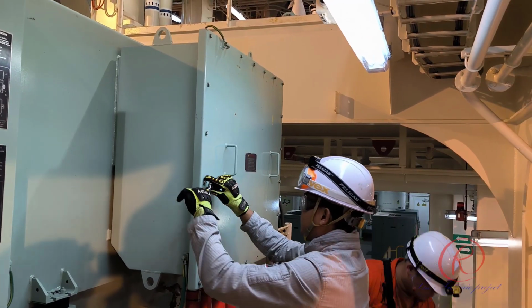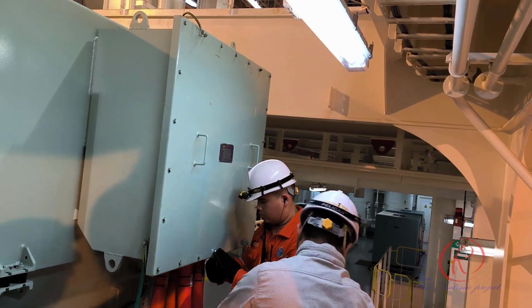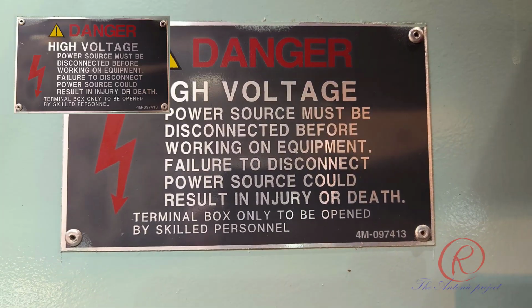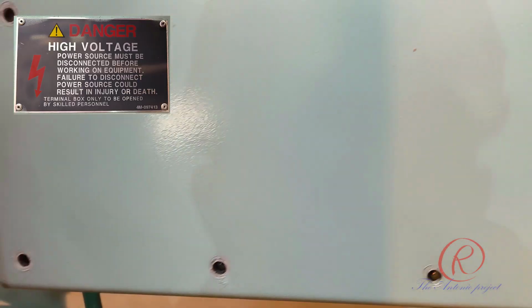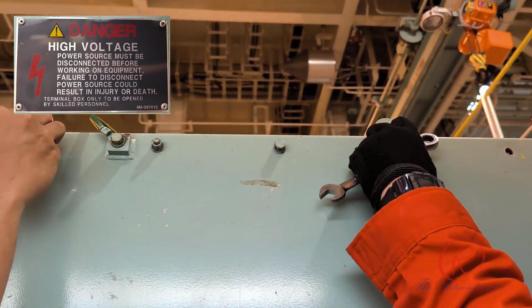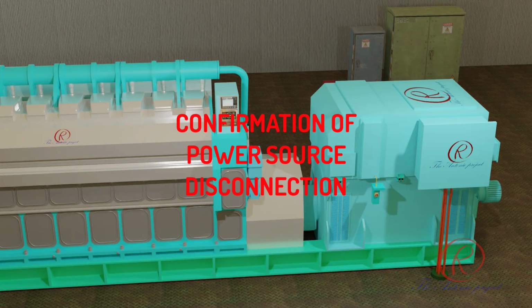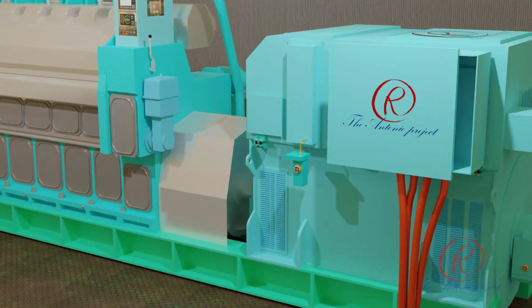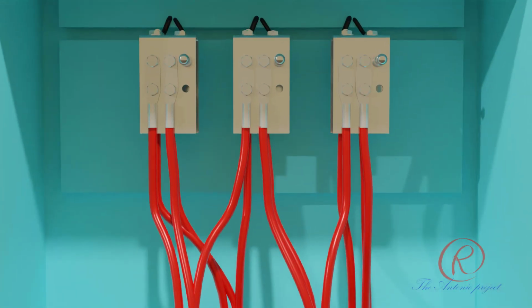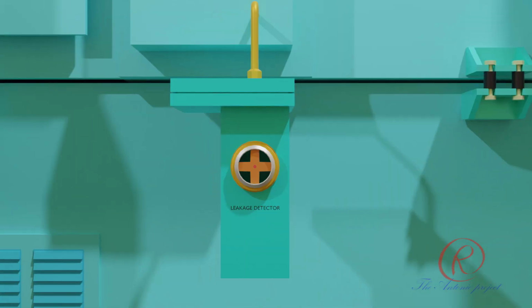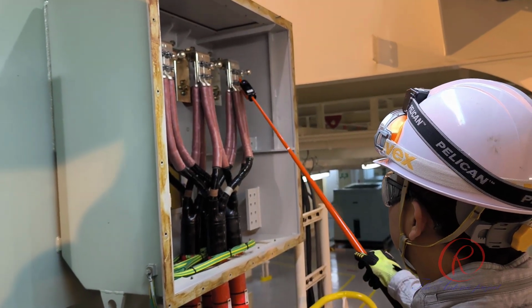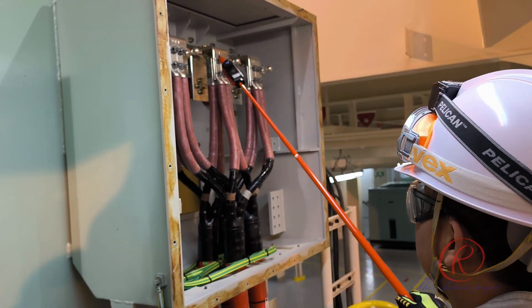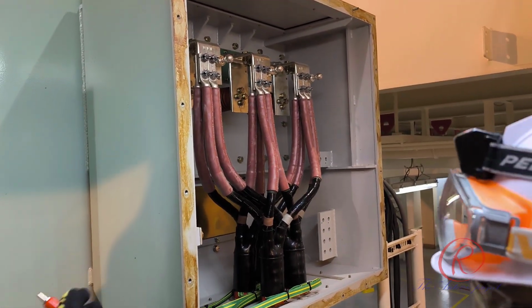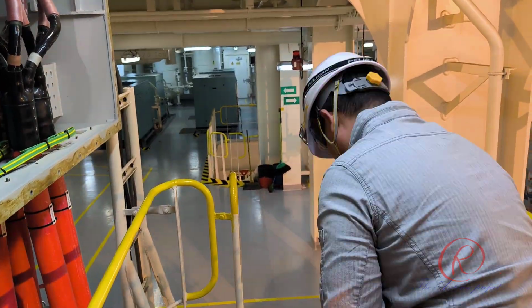Open the cover of the alternator terminal box by unscrewing the bolts. Warning, danger, high voltage. Power source must be disconnected before working on equipment. Failure to disconnect power source could result in injury or death. Confirmation of power source disconnection. Before carrying out any work on electrical equipment, test and measure the existence of power source in the cables or terminals. Using a non-contact high voltage detector, detect the power source at each terminal. Confirm that there is no power source on each terminal using the high voltage detector.